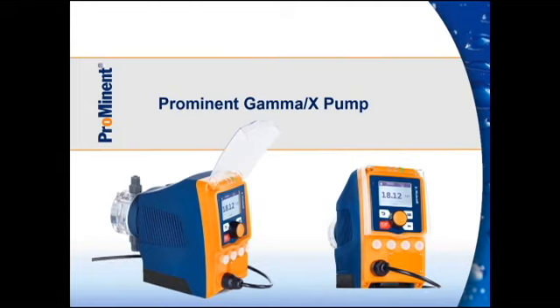One of the main differences between this pump and any pump we've had to date, and you'll hear me mention it numerous times throughout this presentation, is the stroke length, that is the dial typically on the front of the pump. On all of our other pumps, that stroke length has been mechanically attached with that knob on the front. With the Gamma X, that knob on the front is actually a wheel that spins to make selections on the menu. Some of your higher end cars these days have those on the console. You use that to navigate through some of the different menus on those screens. That's what this is going to do. It's a turning wheel that spins, and then you can press it in to confirm selections.